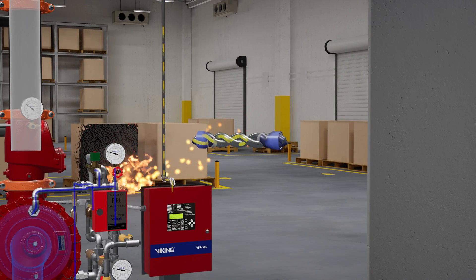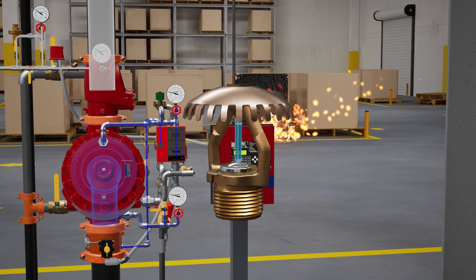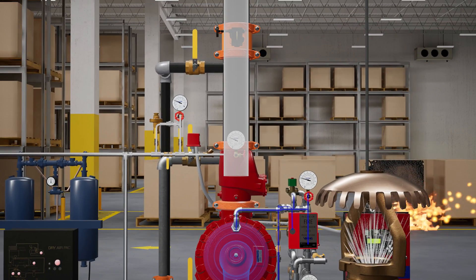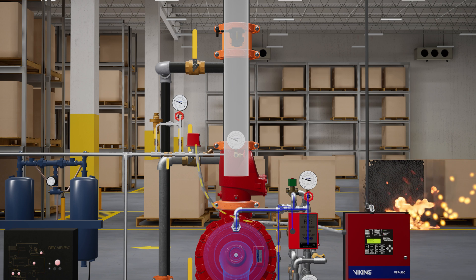Since this is a double interlock system, the system will not activate unless two interlocks are confirmed. As the heat builds and the sprinkler activates, the air pressure in the sprinkler piping is released, activating the PS40 air supervisory switch, which sends a low air supervisory signal to the VFR-300 release control panel.